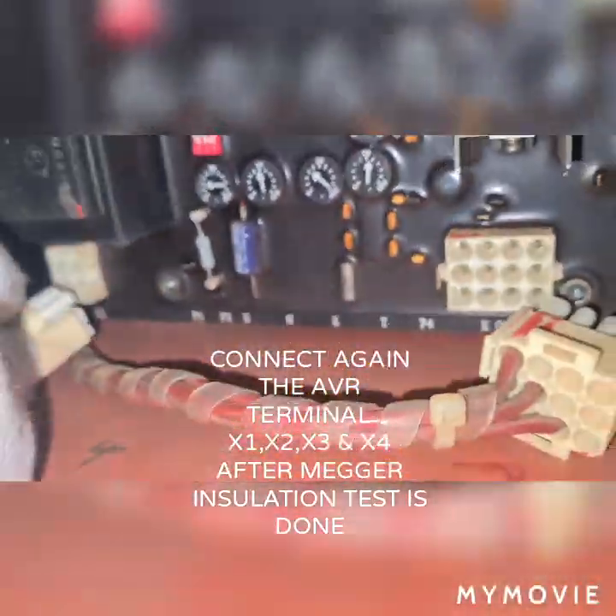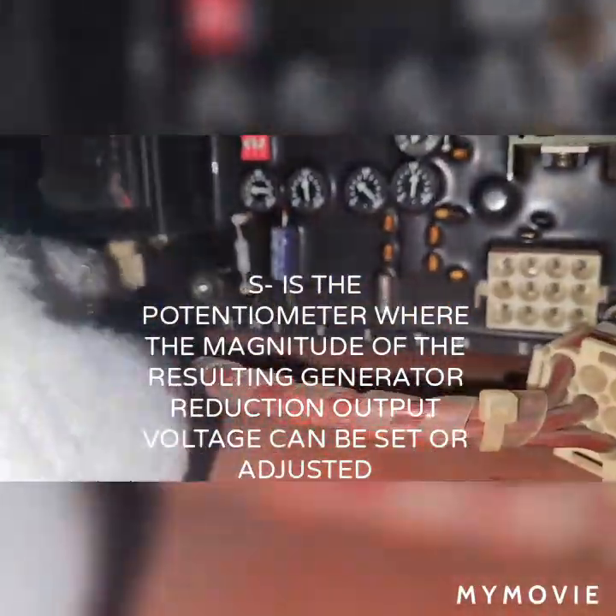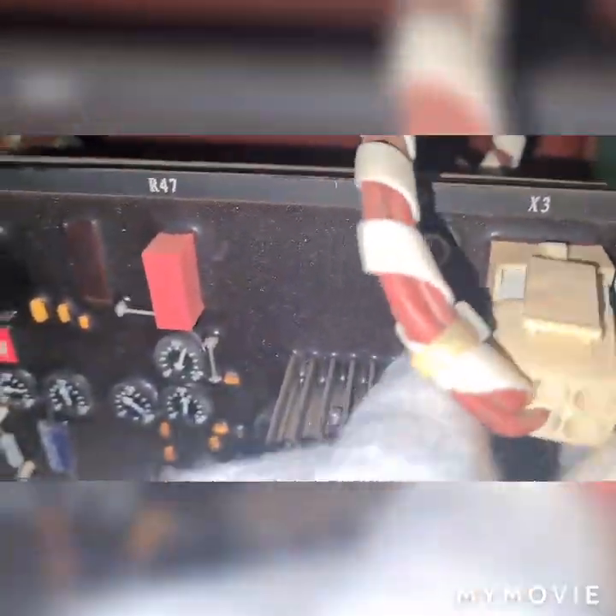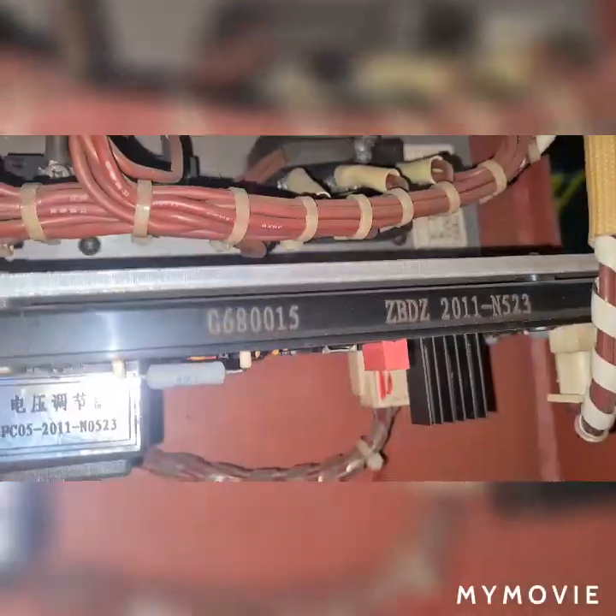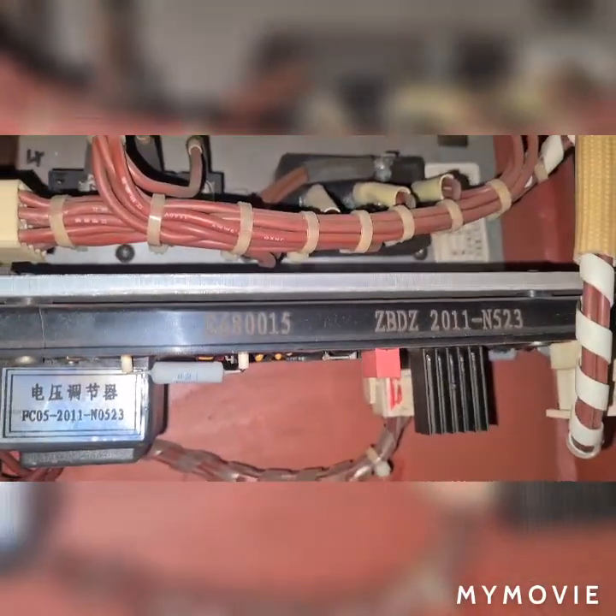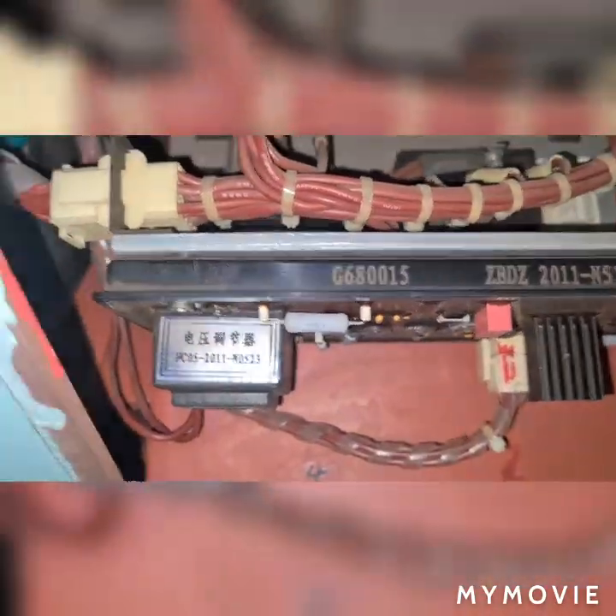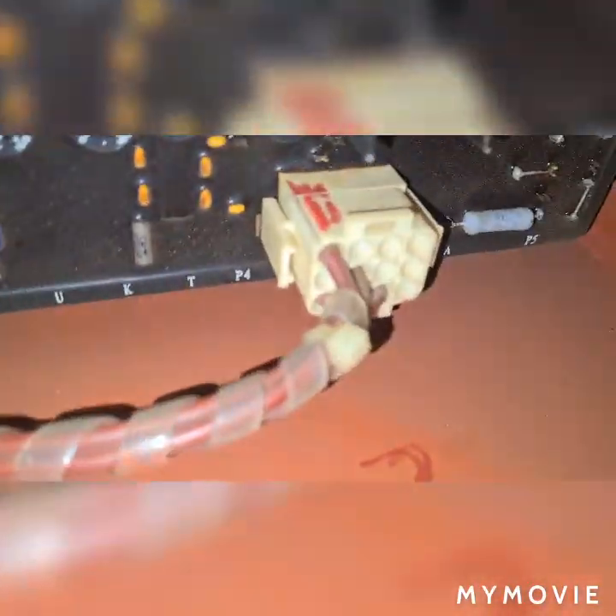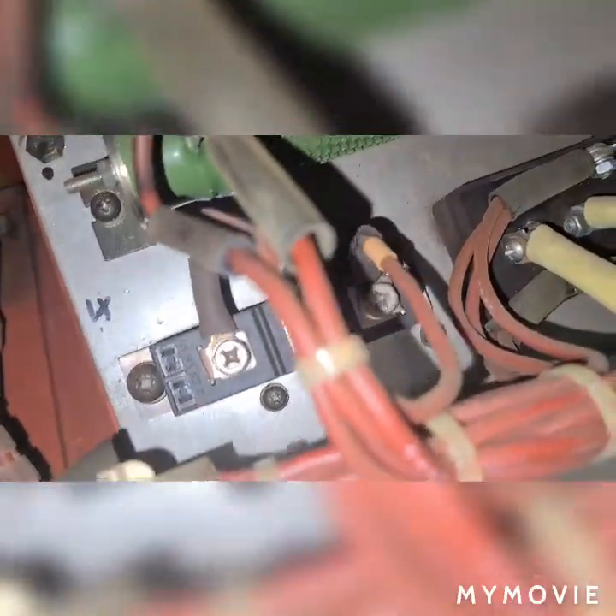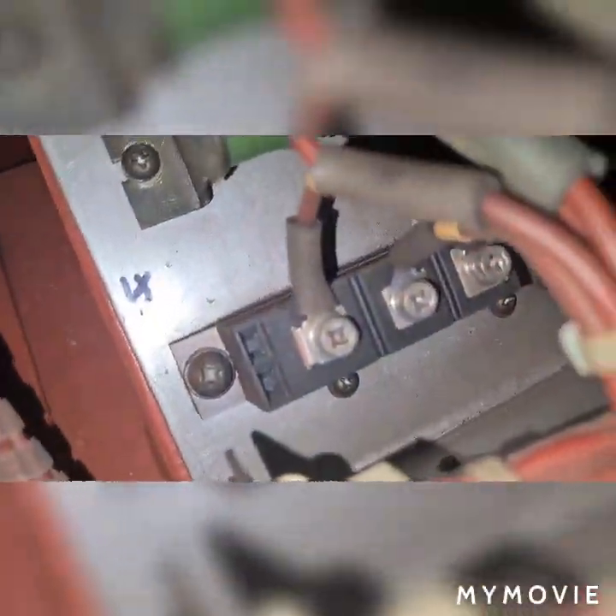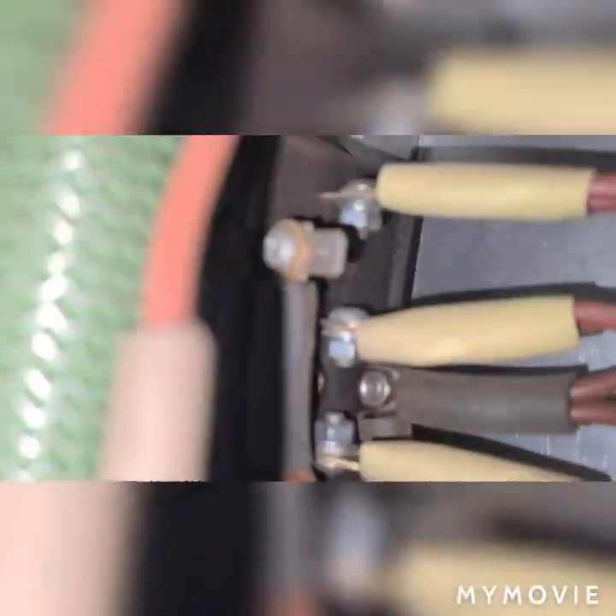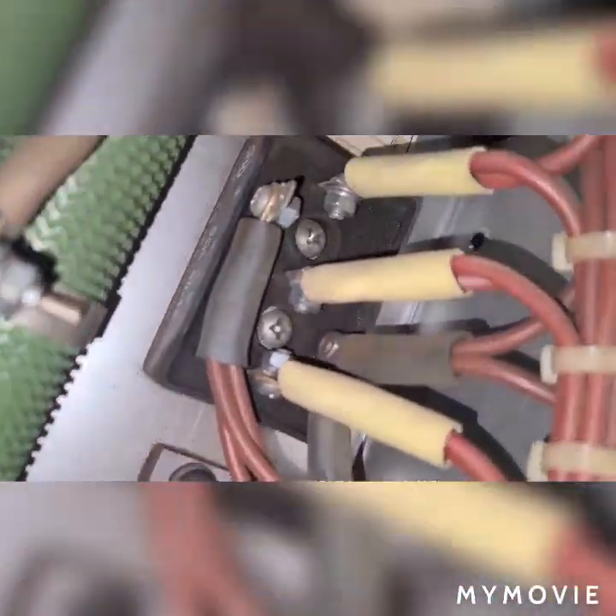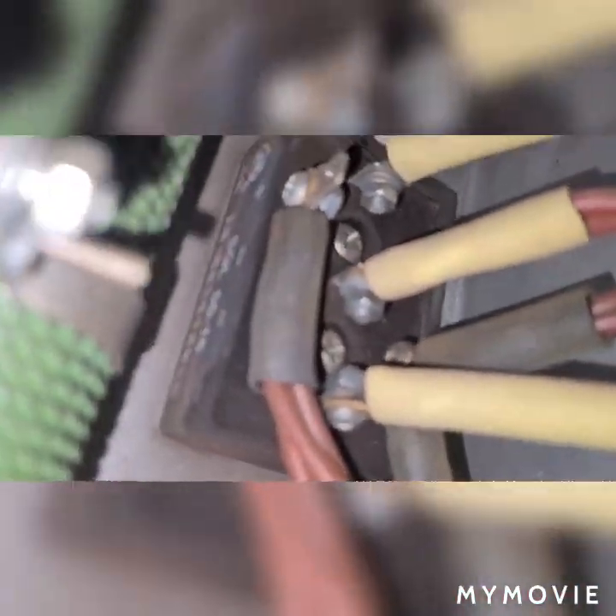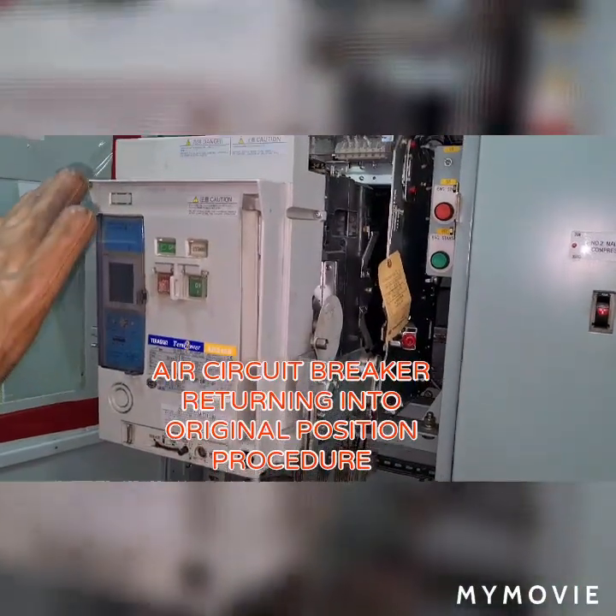Okay guys, since we already performed the Megger insulation check and test, we need to put everything back in the original position, the plugs and connectors of our AVRs. Then after putting it back, we must connect again the circuit breaker which we isolated and pulled out from the main switchboard. Then we need to connect also the fuses, and after this we need to put the control panel on standby mode.